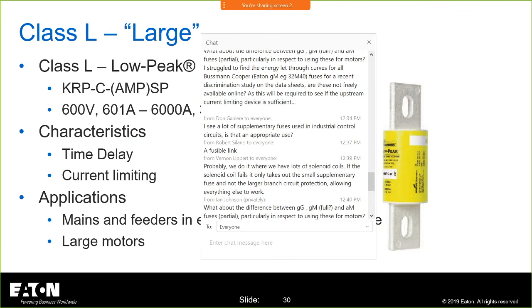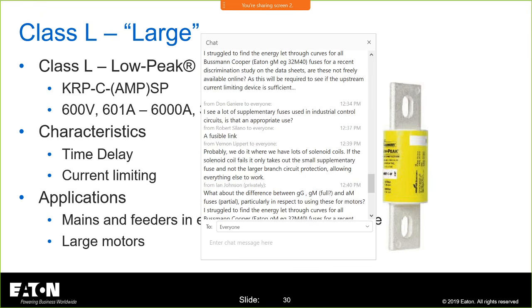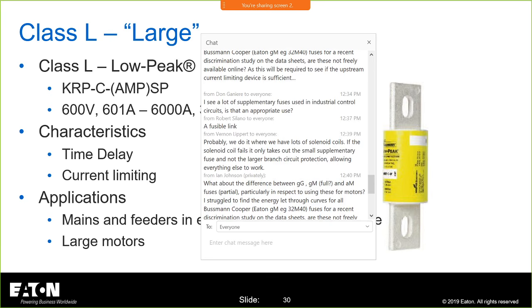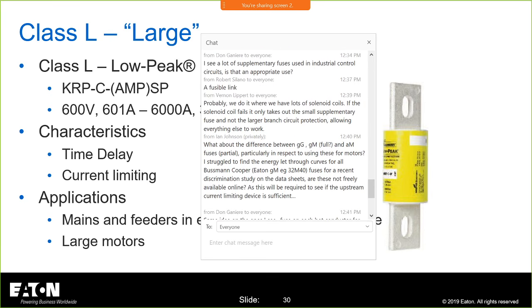I see a lot of supplementary fuses used in industrial control circuits. Is that an appropriate use? Yeah, industrial. As long as it's not being used as a branch circuit type of device, and it's used in a supplementary fashion where there is an upstream overcurrent device protecting the branch circuit, they can use those fuses in those applications. Usually you'll see them in an industrial control panel a lot, like HVAC equipment, things of that nature. As long as they're not being used as a branch circuit overcurrent protective device rated to protect the conductor, and so on.